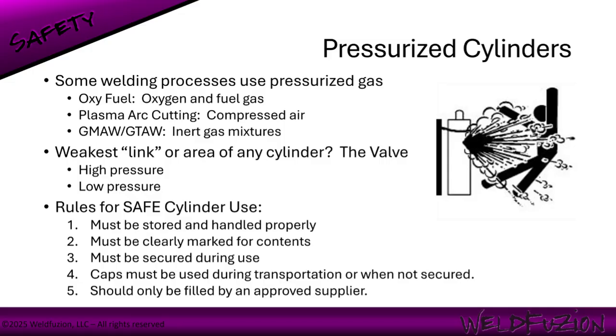High pressure cylinders used to store oxygen, argon, and argon mixes are made from seamless, high strength steel. They have dual seating valves and should be used in the fully open position to prevent them from leaking around the valve stem. Internal pressures of these cylinders can be as high as 2,200 pounds per square inch, or PSI. Low pressure cylinders are used to store fuel gases, like propane or acetylene. These are welded containers made from plain old carbon steel. They do not have a dual seating valve, so it's recommended to operate with the valve open just enough to maintain flow and pressure. That way, it's easier to turn off the valve in case of a fire. And that's the best way to stop a fire. Turn off the source valve.